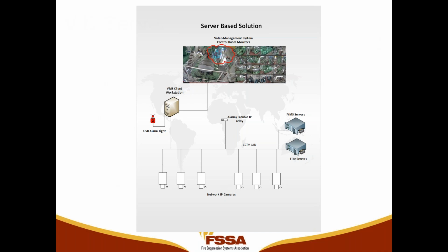In a standard configuration, you have the existing cameras and their server. Add a video analytics server with a relay that activates on smoke or flame alarm. And then when there's an event, video analytics software pops up on the screen indicating the analytics overlay and where the event's taking place.